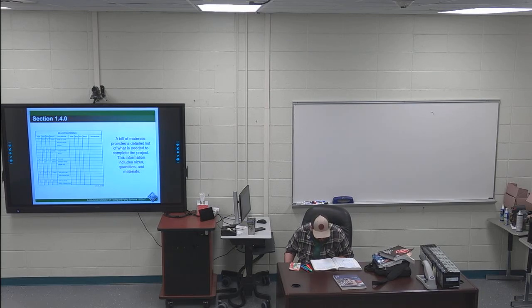A lot of this stuff, look in the material, 316 stainless steel. That's a grade of stainless steel. All this stuff has to be stainless steel. So you can't put stainless steel tubing in a brass fitting because the brass isn't hard enough to swedge onto that stainless steel tubing with your ferrules.